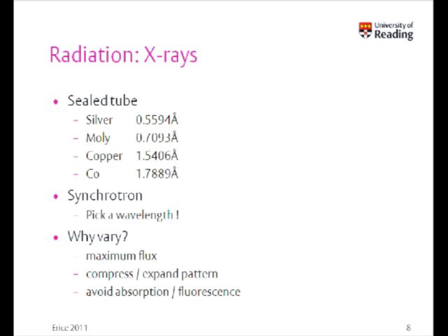You may have reason to compress or expand your pattern. If you collect at longer wavelength, obviously everything is spread out. Although the benefits of compression and expansion depend very much upon the limiting resolution, if, for example, you take a pattern and compress it down, you really need to maintain instrumental resolution high, otherwise you will start to suffer from peak overlap. And of course, by tuning radiation, you can avoid absorption and/or fluorescence issues.